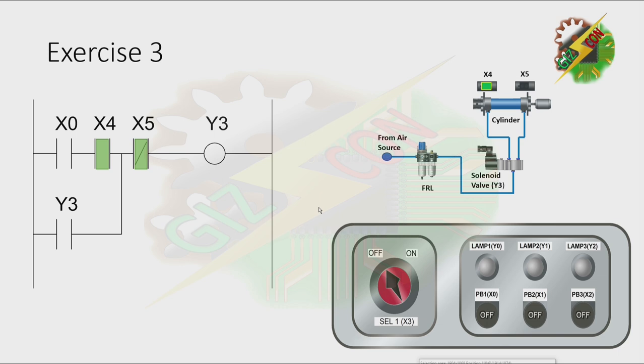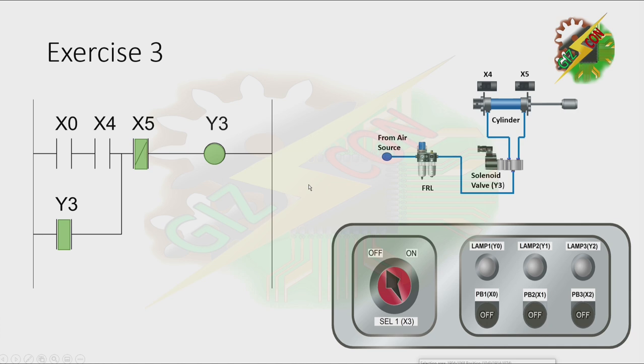This will be my answer to this problem. Let's press PB1. As you can see here, when you press X0, Y will turn on. And because there's latching, Y will not turn off. Even if we press X0, if the cylinder is not at the fully retracted position, it will not turn on. The only way to turn it off is by reaching the fully extended position. Now let's try it again — that's it.